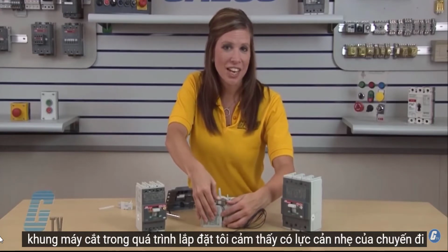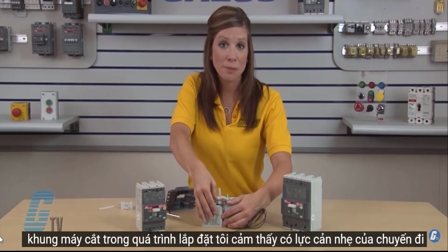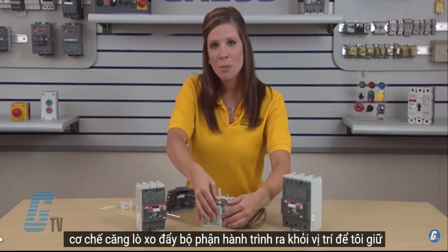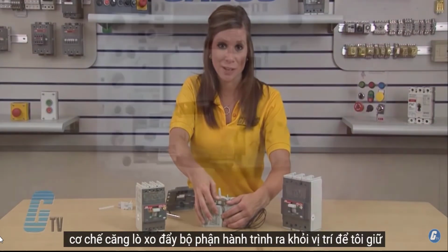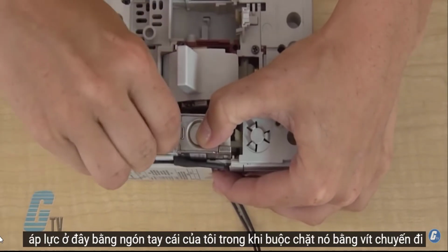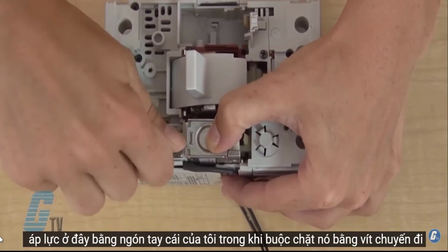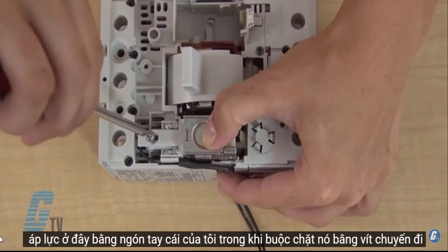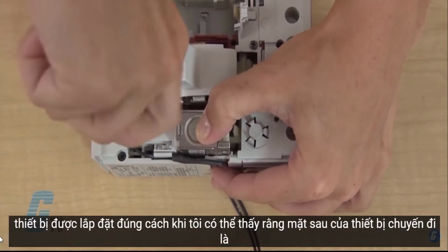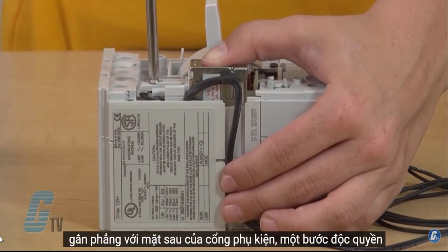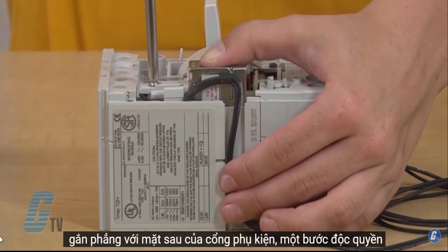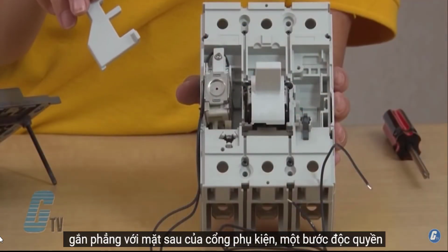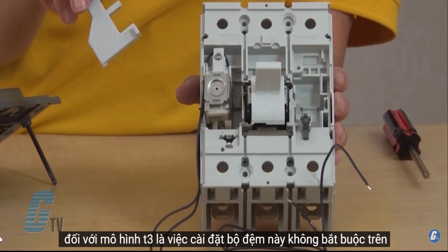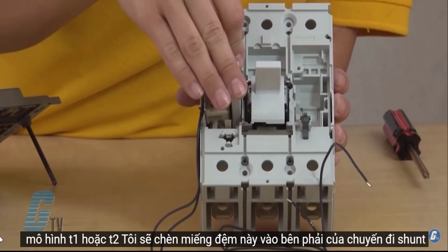During the installation, I feel slight resistance of the trip mechanism's spring tension, pushing the trip unit out of position. So I keep pressure here with my thumb while fastening it with the screw. The trip unit is properly installed when I can see that the back of the trip unit is mounted flush with the back of the accessory port. A step that is exclusive to the T3 model is the installation of this spacer, which is not required on the T1 or T2 models.